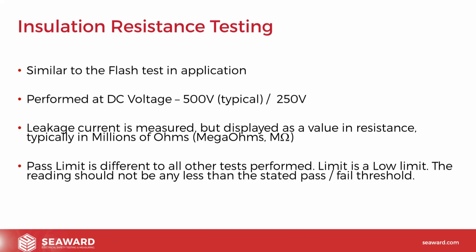However, when I was talking before about the surge protected devices, it's typical that the operating voltage for these suppression devices kicks in at around 300 volts. So performing the test at 500 volts will still trigger this kind of failure. So we should perform the test at 250 volts if we know the product has surge protection. Again, it comes back to a statement in the code of practice about being reasonably practicable. What can you do to the product to ensure safety? In some instances, it's just not possible to perform that test at as high a voltage as we would like. So we have to find an alternate method that will at least give us some confidence that the product is safe.